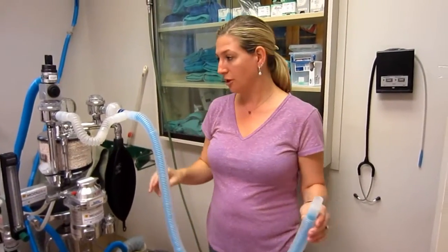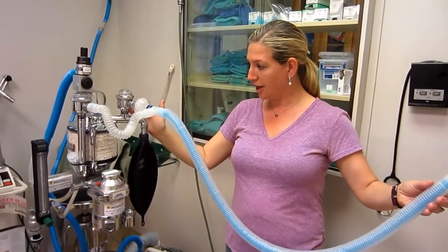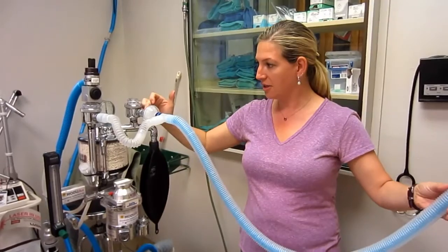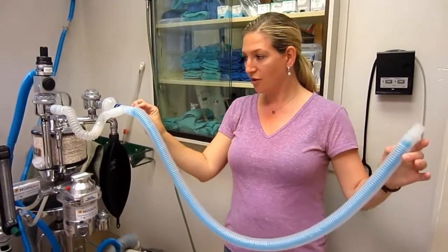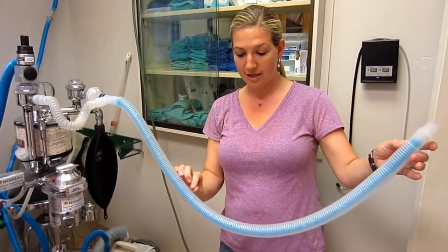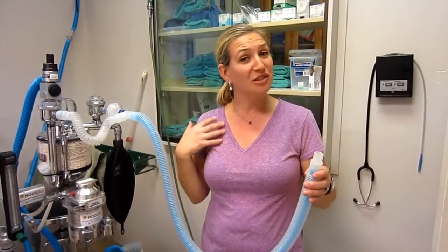So how this works, and I know I just described it a little bit, but when the oxygen and isoflurane come into the inhalation tube and are delivered to the patient, it comes down this blue corrugated tubing on the inside and delivers to the patient. The patient exhales. When the patient exhales, it's exhaling a little O2, carbon dioxide, as well as the isoflurane gas. And it's warmed because it's gone through the lungs, so it's a little warm, and there's a little bit of moisture with it.